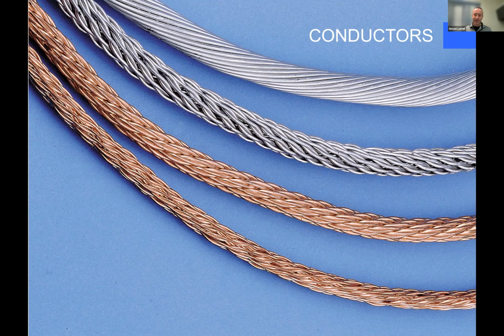We're going to use thicker lightning rods. We're going to use thicker, more robust cable. That's why we have those two different sizes. And the cutoff for that is 23 meters. The thing that always bugs me is when a building's like 22.5 meters. I'm like, all right, it's class 1, but then they put an HVAC unit on it that's 3 meters tall. I'm like, no, it's class 2. And class 2, that's more expensive material. But that's a problem for me as a designer and a bidder, not necessarily for you all as inspectors. Just know if it's above 23 meters, we're using a heavier grade of lightning protection component.